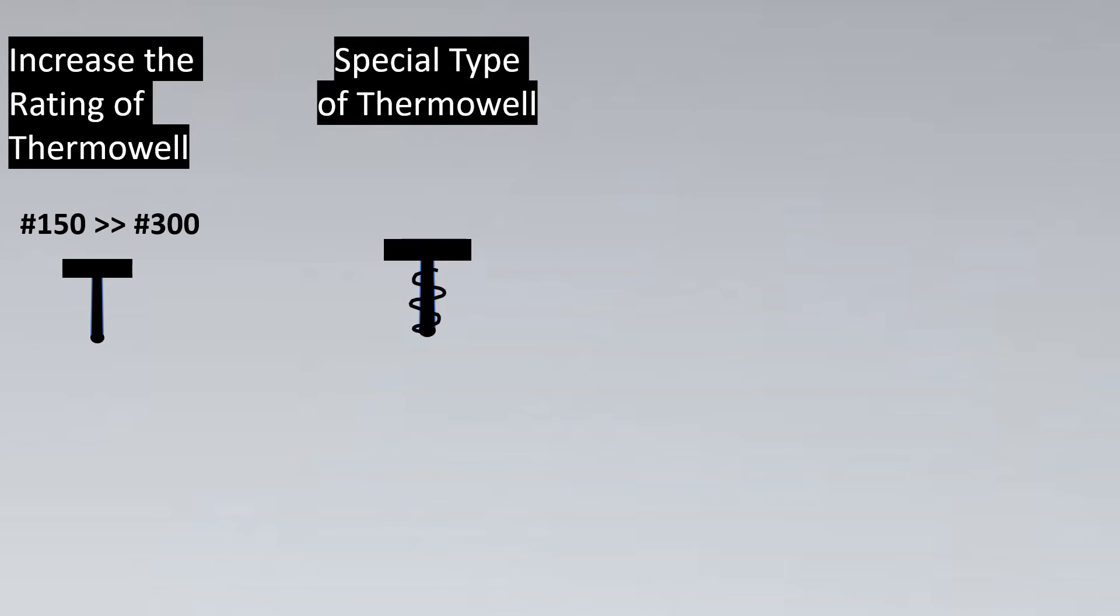The next thing that we can use is increasing the rating of the thermowell. This indirectly is increasing the schedule or thickness of the thermowell. What if we go from 150 rating to 300 rating? Yes, that is another option that can be used.